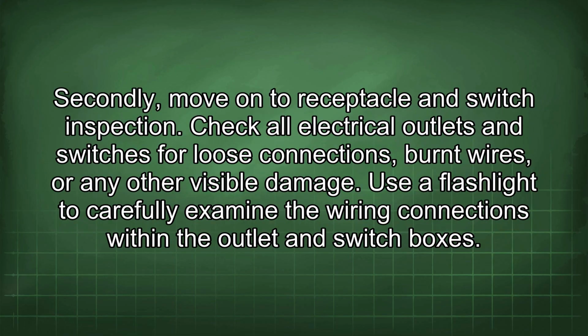Secondly, move on to receptacle and switch inspection. Check all electrical outlets and switches for loose connections, burnt wires, or any other visible damage. Use a flashlight to carefully examine the wiring connections within the outlet and switch boxes.